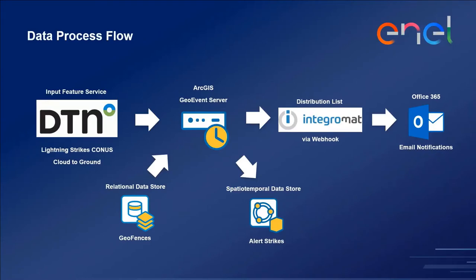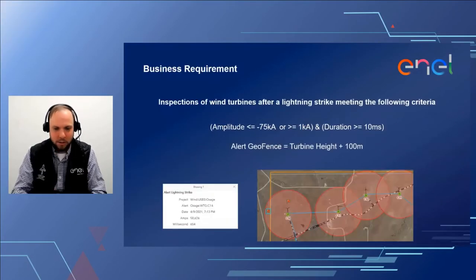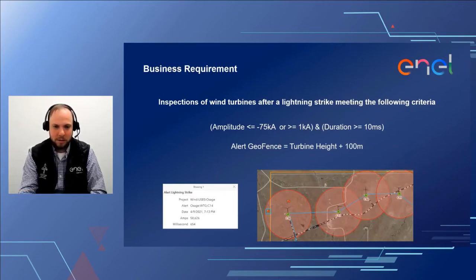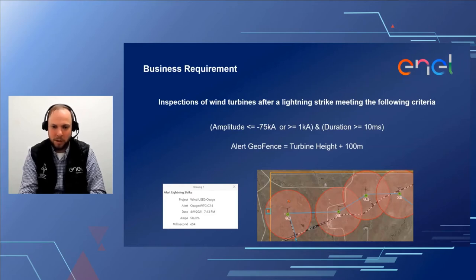Our ArcGIS GeoEvent Server is monitoring that feed coming from DTN, along with the geo-fences of the particular turbines we are monitoring from our relational data store. You can see those red circles around each wind turbine—those are the alert areas for a critical lightning strike. That's the turbine tip height plus 100 meters, which is the spatial accuracy of the lightning data supplied by DTN. So there's a pretty high probability that if a lightning strike took place inside that radius, it hit the wind turbine.